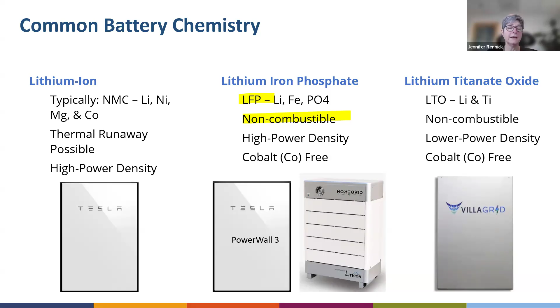And then there's the lithium titanate oxide batteries, also non-combustible, with a little bit lower power density. It's also cobalt free. So those are the new chemistries out there. Batteries are improving and fire is less of an issue, but you still might be dealing with some of the old battery chemistries, especially in existing buildings that already have their batteries.